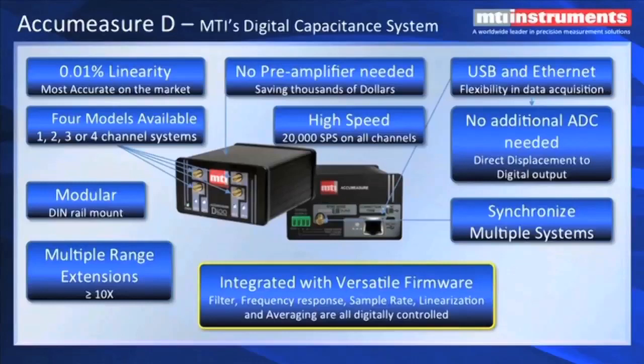Another important point is no preamplifiers needed. We can drive up to about 20 meters of cable without having to add a preamplifier. It's got a very high sample rate, in excess of 20,000 samples per second on each of the 4 channels simultaneously. It's got both USB and Ethernet outputs, so you can choose the best communications method for your application.